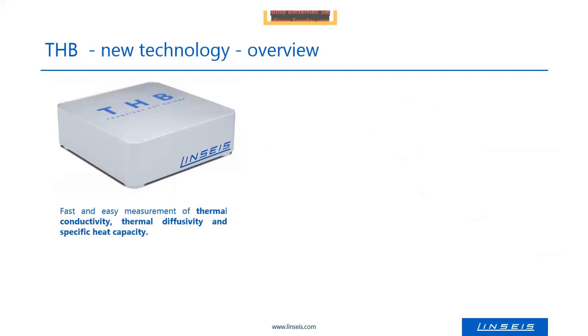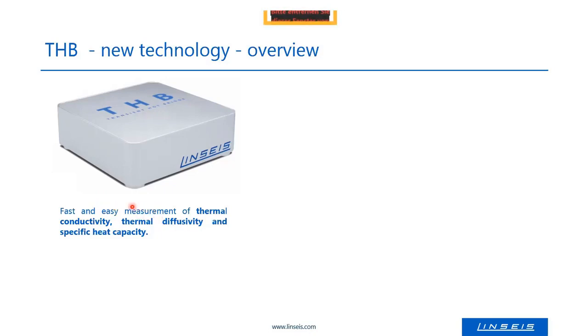The transient hot bridge is a hot wire technique, and the good thing is that you get directly, as a result, the thermal conductivity. That's not the situation for optical methods like laser flash, where you get the thermal diffusivity as a result, not the thermal conductivity. But also with the THB, we can measure the thermal diffusivity. And if we know the density of the material, from the thermal conductivity and diffusivity we can also calculate the specific heat capacity, which is quite useful information.